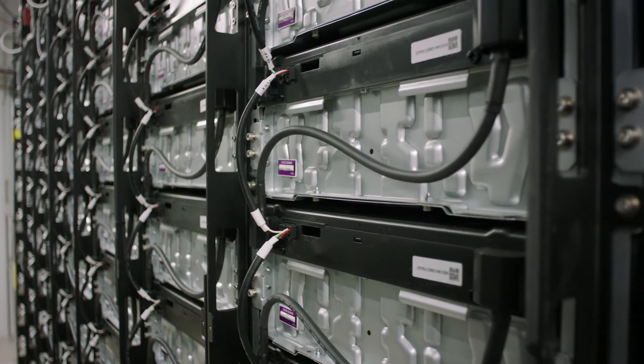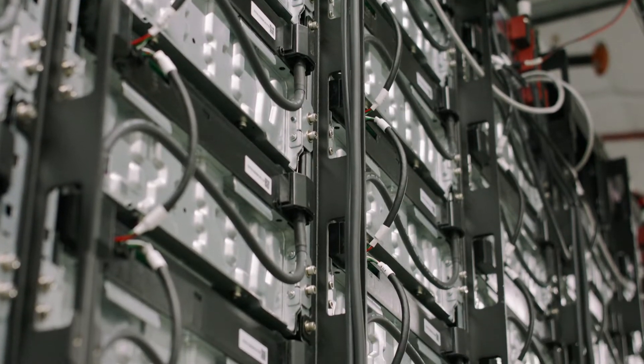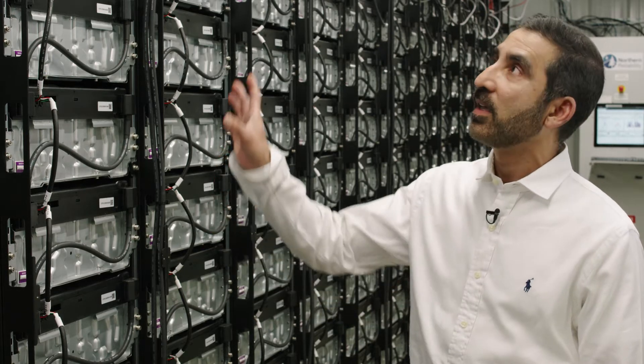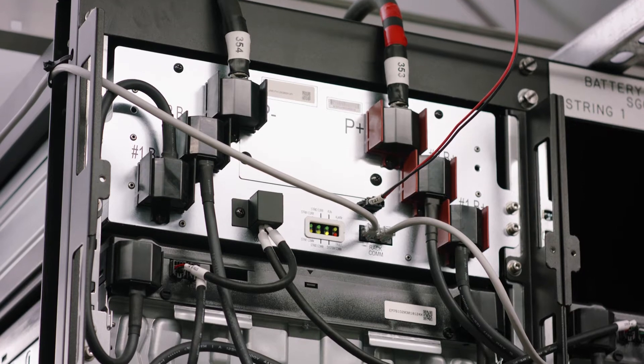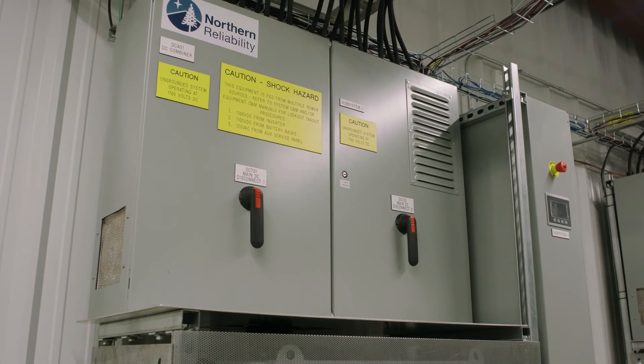What you see here is the dual rack system, and there are 12 of those. Each dual rack consists of two columns, also called strings. The output of both strings is connected to the switchgear. Switchgear monitors the performance of each module via these communication links. In the event that any module malfunctions, the switchgear will isolate all those modules from the rest of the system. The output of the switchgear is then fed into the DC aggregator, which is then connected to the inverter.